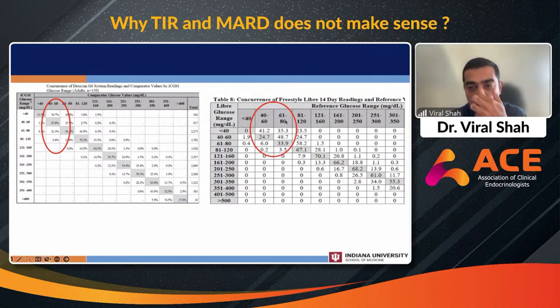Now let's look at another one. That's a 60 to 80 milligram per deciliter venous glucose. 33%, or 34% precisely if you want to round it up, of the time it's going to say you are at 60 to 80 milligram per deciliter. But almost 50% of the time, it's going to say you are lower than 60 to 80 milligram per deciliter. So this sensor is biased towards the lower side.